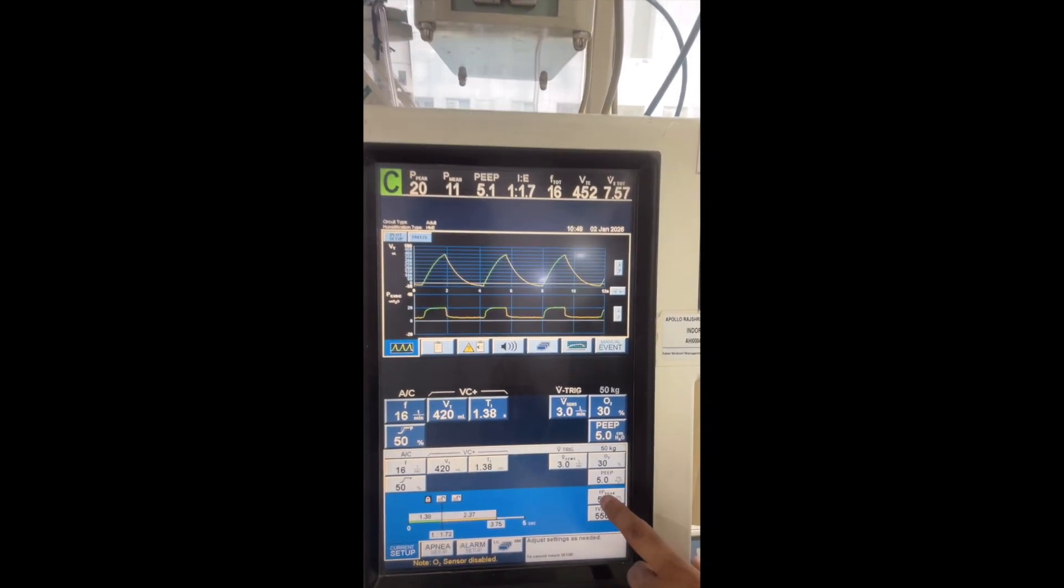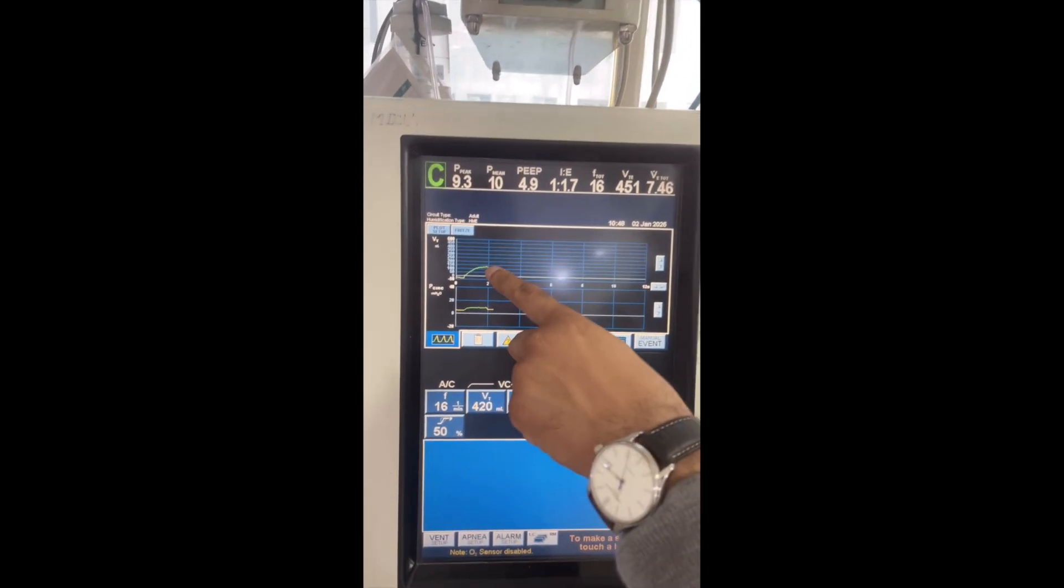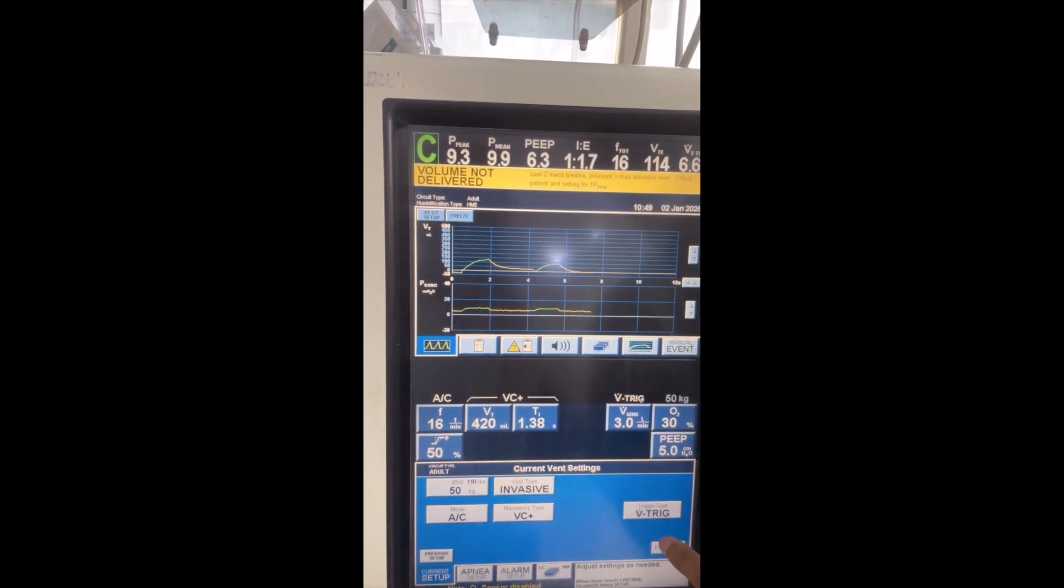I'll just show you by adjusting. Suppose I cut off the pressure to 12, so it will not deliver the tidal volume now. Not delivered.